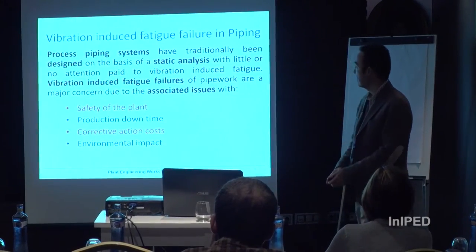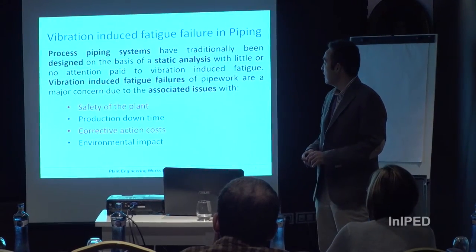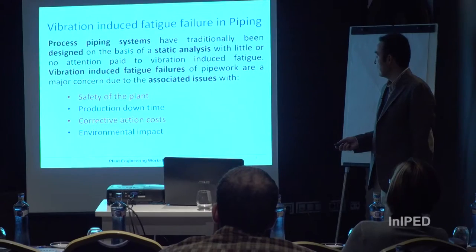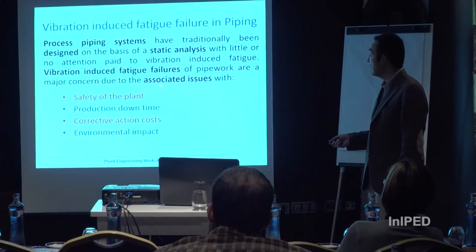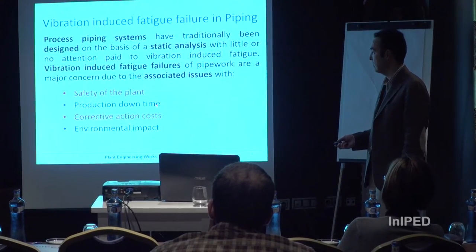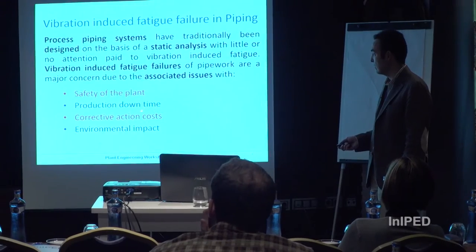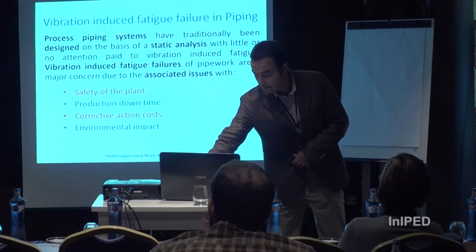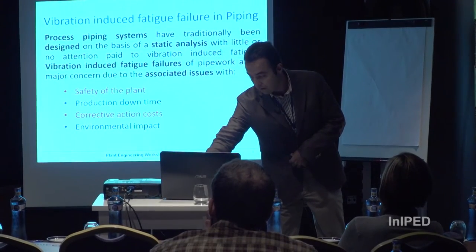Traditionally, piping systems have been designed on a basis of static analysis with little or even no attention to vibration-induced fatigue and dynamic analysis in general. Only some main or complex systems are subject to dynamic analysis. Vibration-induced fatigue failures are a major concern due to associated issues: the safety of the plant, production downtime, corrective action costs, and any environmental impact — of course, if leakage associated with cracks is found.